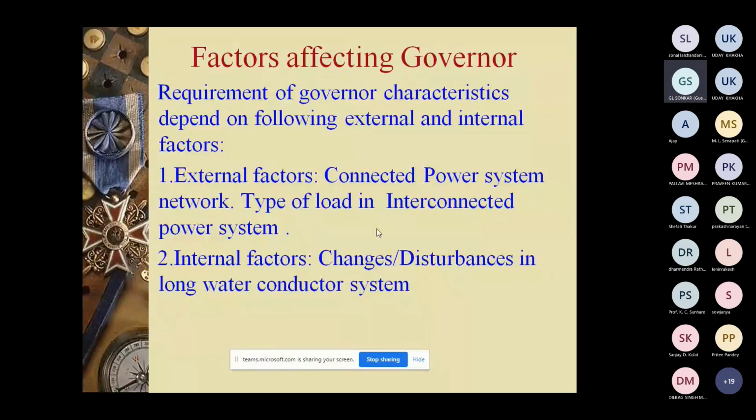So depending upon that, you may be controlling the runner speed, but at the same time you are not able to control the positive pressure developed in the spiral casing. So in that particular case, you have to install some pressure release valves in the water conductor system, or where you are getting some positive pressure developed. It is mostly on the spiral casing only.